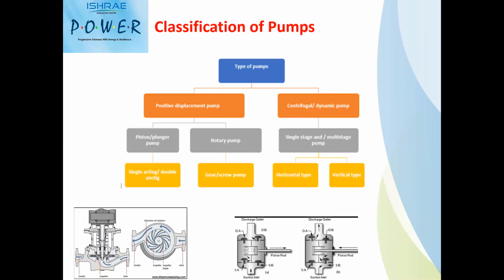And in case of gear pumps, the rotation between the gears physically shifts the liquid from one position to another position. So positive displacement pumps are generally where there is a physical action exerted on the fluid to transfer it from one level to the other level or create the pressure. In case of positive displacement pumps, generally these pumps are used for transferring viscous liquids or heavy liquids, and generally these pumps are not used for water transfer applications.